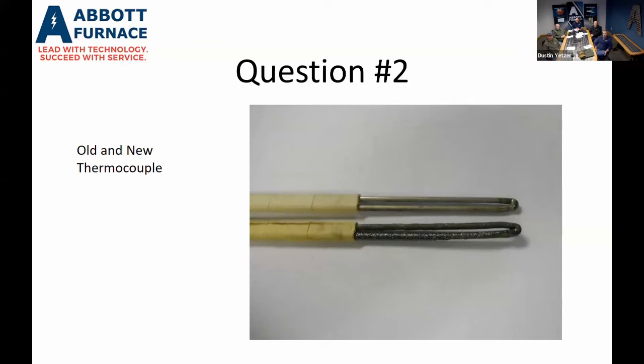If you run a furnace over 1700 degrees F, we recommend changing your type Ks out every 3 months because it starts to drift the temperature that the thermocouple to the instrument sees. On a 2050 furnace, that temperature usually is about 30-degree drift in 3 months. If you're below 1700 degrees, you can get about a year out of a type K thermocouple without that 30-degree drift.